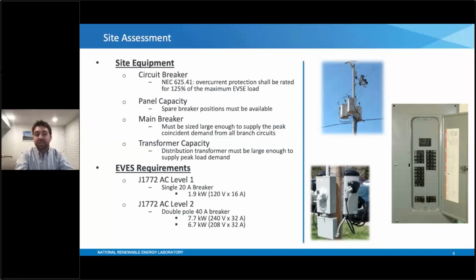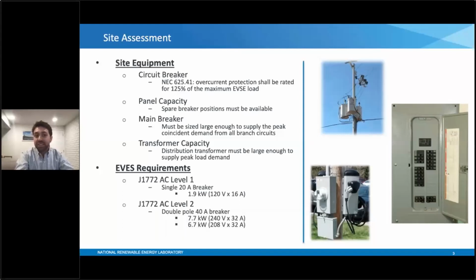And the same can be said for a 208 volt service. It's very common in commercial applications. It also requires a double pole 40 amp breaker. So just to summarize things, if you're installing a quick, small little level 1, you only need a single breaker position and a 20 amp breaker, whereas level 2 actually, it's about twice that typically. It's most common where you require a double pole, so 2 breaker positions, and you'll need a 40 amp rating typically for those units.